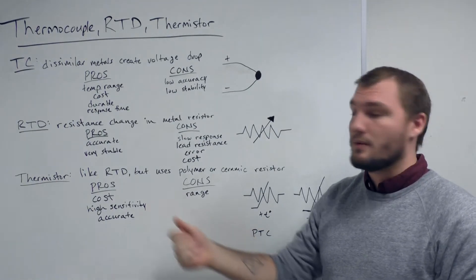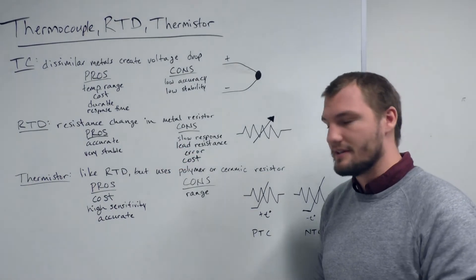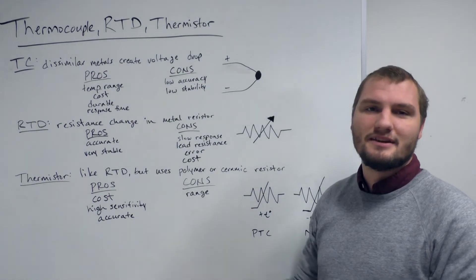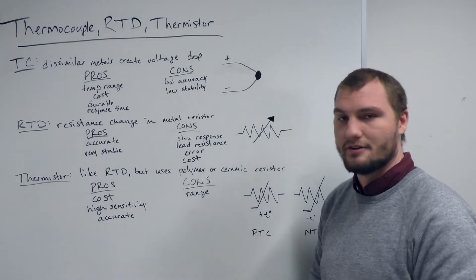In terms of sensitivity, whereas RTDs are in the milliohms per degree C range, thermistors tend to be hundreds or thousands of ohms per degree C.